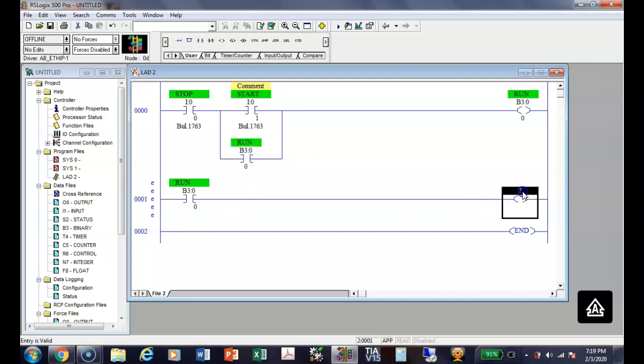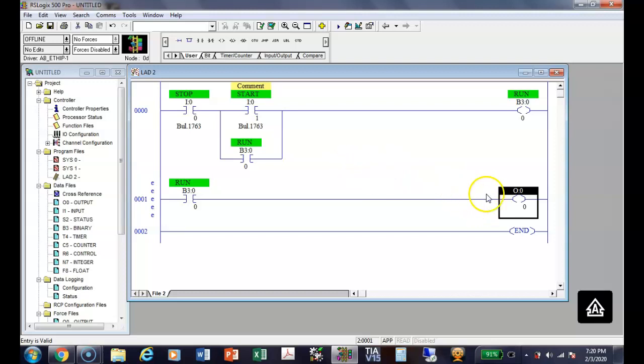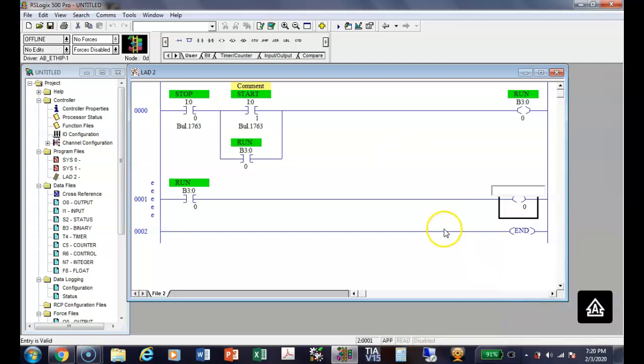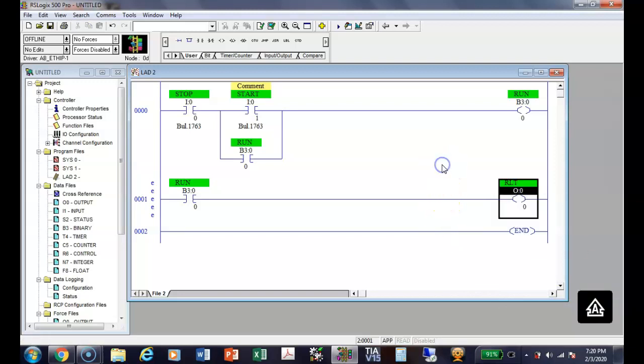So here I want to assign this to an output. So I'm going to say out colon zero slash zero. So why can I use zero here and use zero there? Yeah, we're in a different data file, right? Does that make sense? So you're right. So we have output zero and we have input zero. Then I've clicked off of it without assigning a symbol. So how would I go back and assign a symbol now? I'm going to right click on it, choose what, edit symbol, and then we can give it some name. Everybody okay.